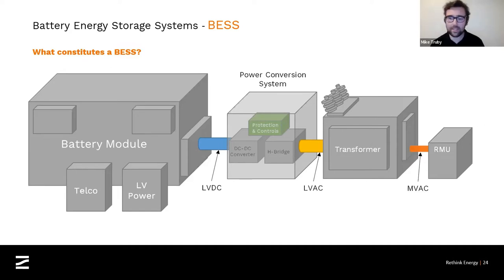That transformer will then normally be connected into some kind of ring main unit. What this allows us to do is to connect numerous battery modules together in either a radial or a ring topology to connect into our MV switchgear. It means that we can isolate individual modules if we need to do maintenance on them, if there's a fault, or we would like to replace part of it. And it also means that for systems that need higher redundancy, we can reconfigure our system in real time if there is a fault at the MV level.